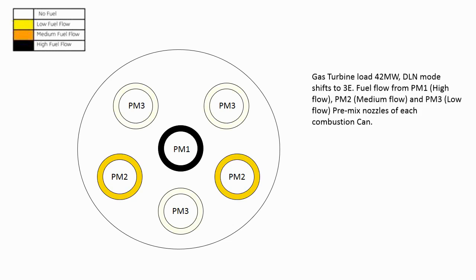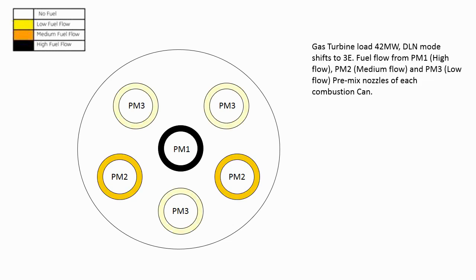When 7FA gas turbine load reaches 42 megawatt, DLN mode shifts from mode 3 to mode 3E. Fuel flows from PM1, PM2, and PM3 of each combustion can. Note that fuel flow is high from PM1, medium fuel flow from PM2, while from PM3 fuel flow is low.